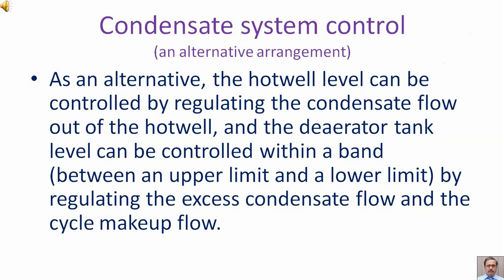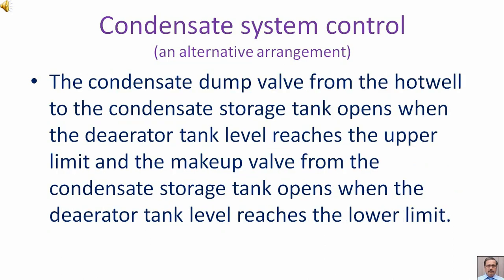As an alternative arrangement, the hot well level can be controlled by regulating the condensate flow out of the hot well. The deaerator tank level can be controlled within a band between an upper limit and a lower limit by regulating the excess condensate flow and the cycle make-up flow. The condensate dump valve from the hot well to the condensate storage tank opens when the deaerator tank level reaches the upper limit, and the make-up valve from the condensate storage tank opens when the deaerator tank level reaches the lower limit.